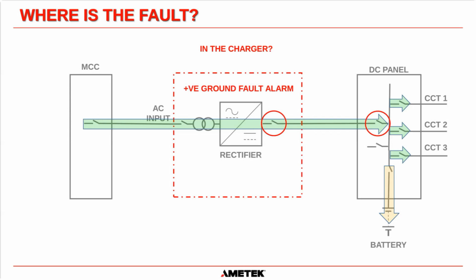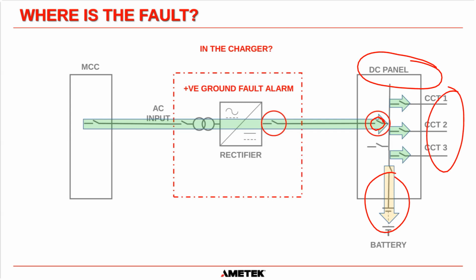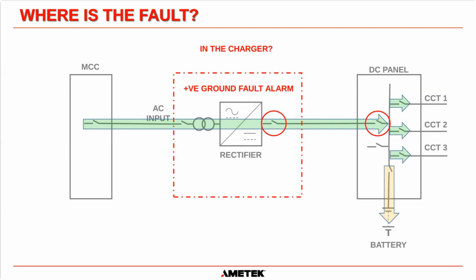If you open this breaker here and the fault disappears, we have now isolated the fault. It's either in the DC panel, it's in the battery, or it's in the load circuits. So we're getting somewhere, okay? So let's say we've opened both of these breakers and the ground fault alarm disappeared. That means we know it's either in the DC panel, the battery, or the load circuit.